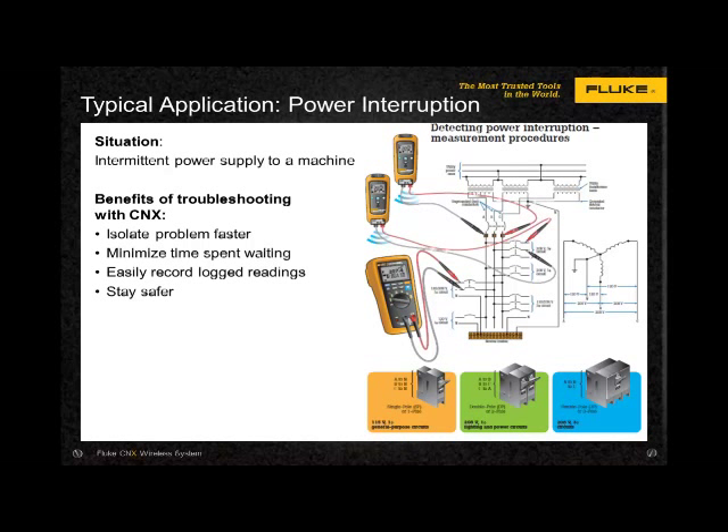Detecting intermittent power interruptions and nuisance tripping can be troublesome and time-consuming. Determining which component is at fault and where the problem is — even harder. Some issues can be outside your control, from load switching at the utilities, causing problems with incoming power to your facility. Testing should be dynamic while the loads are under normal operating conditions, not static, testing only discrete components. Using the CNX modules and logging readings quickly allowed this customer to drill down to the culprit and replace the defective breaker.